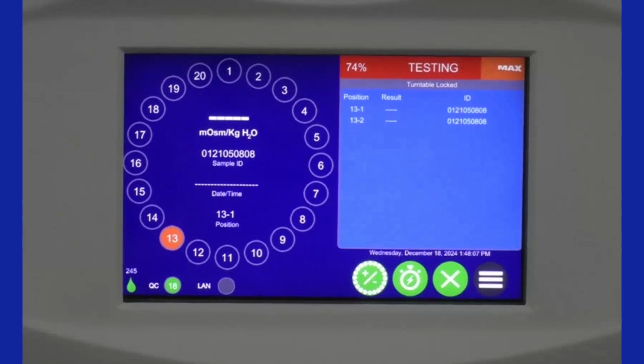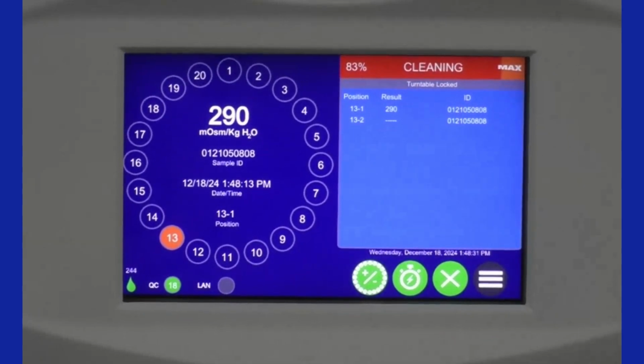And then after it finishes sampling, whatever sample that it's on, after it finishes aspirating that sample and completes that testing, it will actually move over to position 11, where I loaded my stat test, and ignore everything from 4 to 10 that is programmed as a routine test to prioritize that stat sample in the queue. So another really great feature that helps us make sure we're turning the results around for the patients that need it fastest, where their potential treatment for a toxic alcohol ingestion is on the line. So that's another really great feature of this instrument as well.